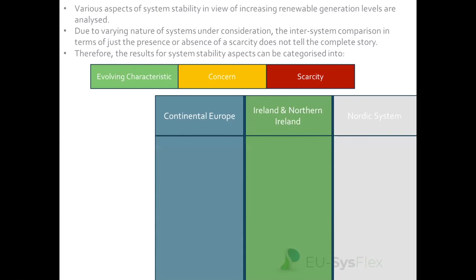Similarly, frequency containment is an evolving characteristic in all systems, but for the all-island system it must be noted that the current FFR product number one has been included, and we already had a mitigation for the inertia scarcity in place to enable us to run the frequency stability evaluations. So a mitigation in terms of frequency containment has already been applied when running these simulations. And still we end up with an evolving characteristic, especially interestingly in the low renewable scenario, because in the low renewable scenario we have a smaller number of fast acting reserves.